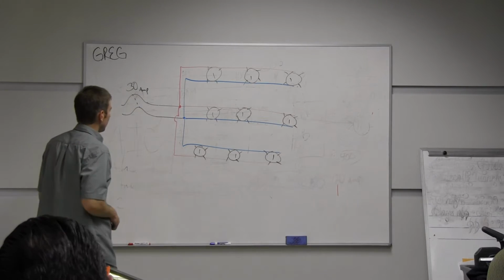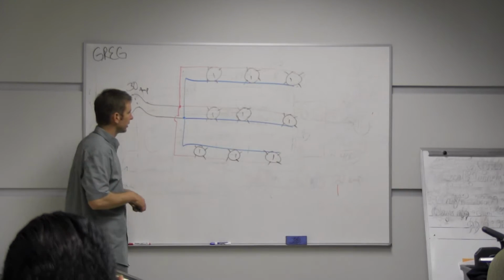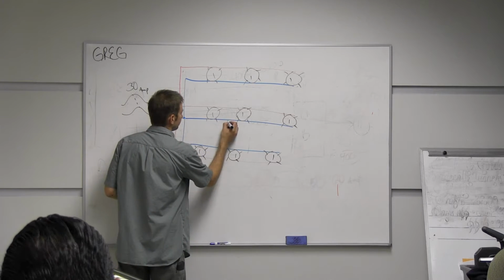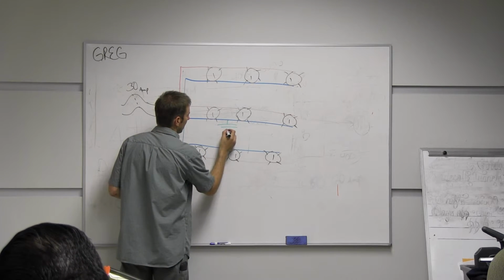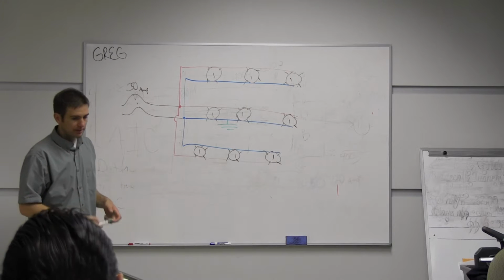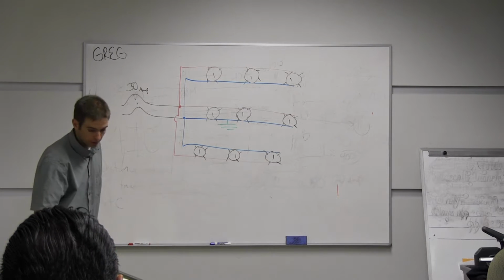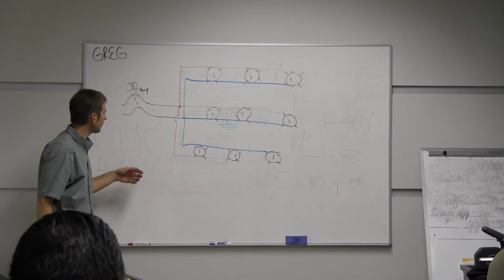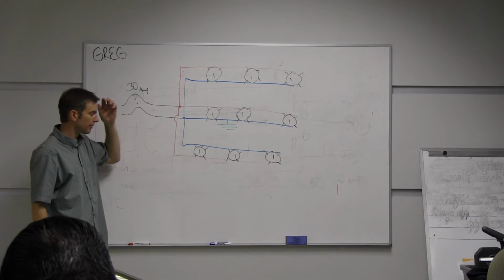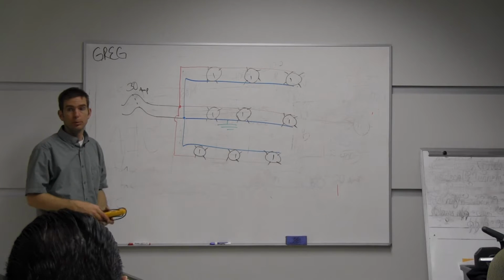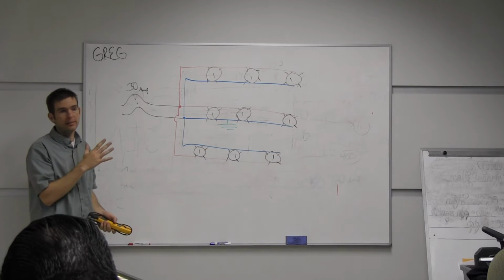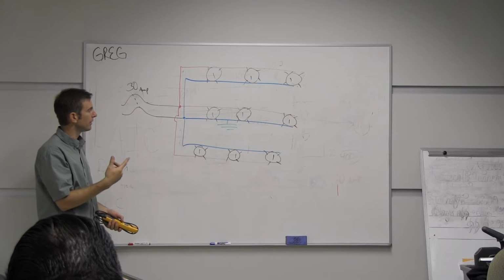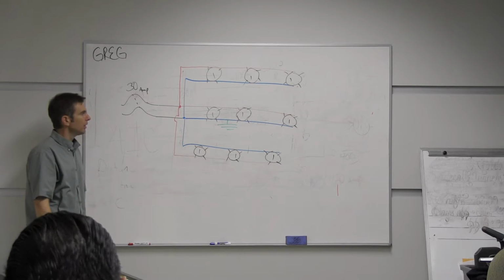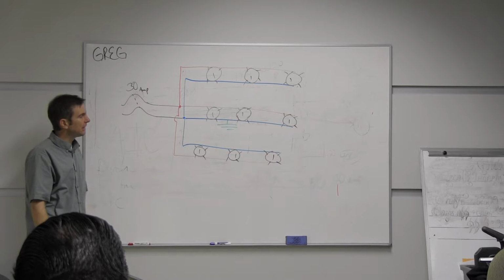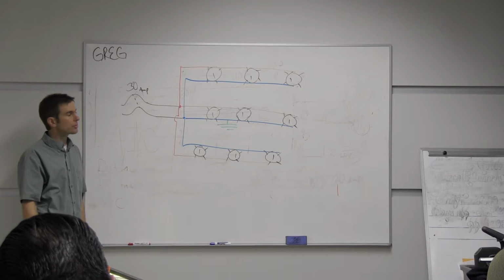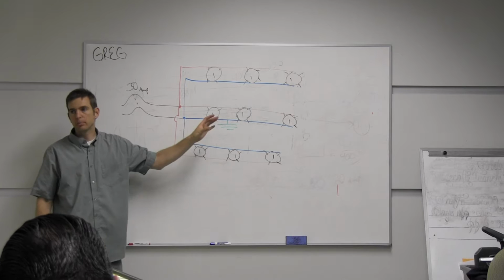So we get a call out. We're all going to show up. All the lights are dark for some reason. Something happened. I'm going to draw to you what happened, but let's find out how we can determine what happened. So the circuit breaker trips. The power's off. As I said, we turn it back on. The circuit breaker takes 5 seconds to trip again. 1, 2, 3, 4, 5. It trips again.